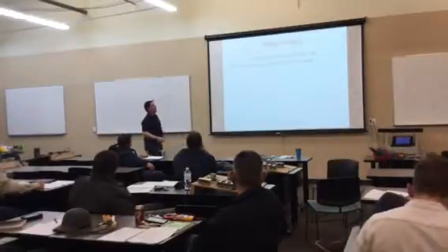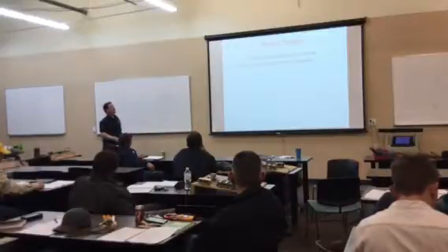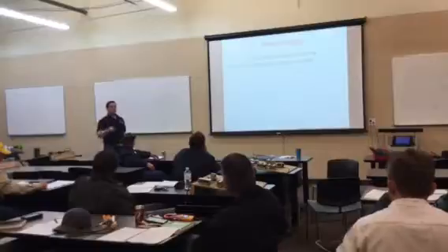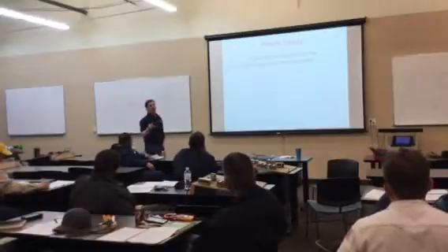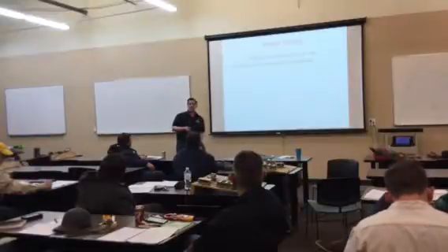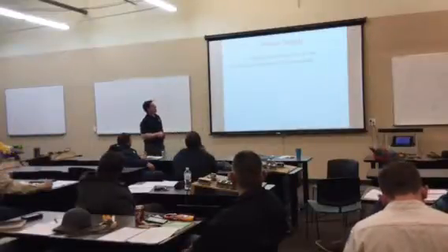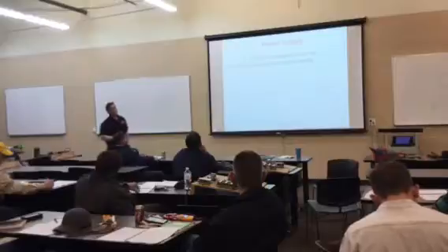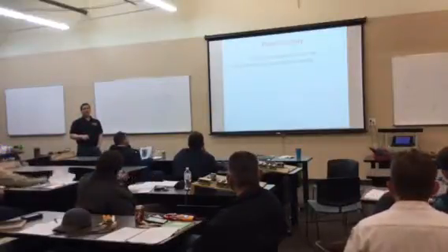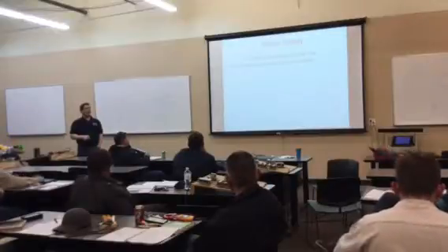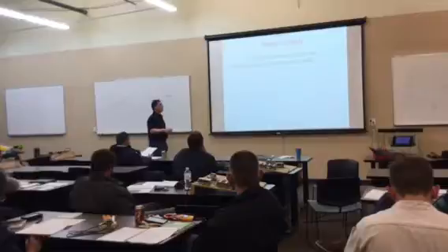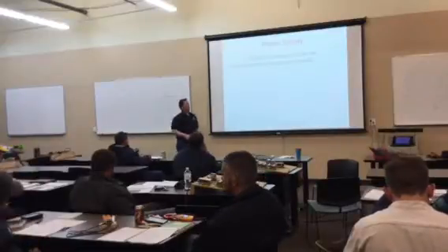Power supply, voltages in the field. How do you recognize one voltage from another before you get your meter out, so you know what to expect? There are color codes present. They're not always followed, but when they're followed, this is what they are. For 120 volts AC single phase, you have one colored wire and one white wire. The white wire should be the neutral or 0 volts in relationship to ground. The colored wire should be your hot one or 120-ish volts in relationship to ground.